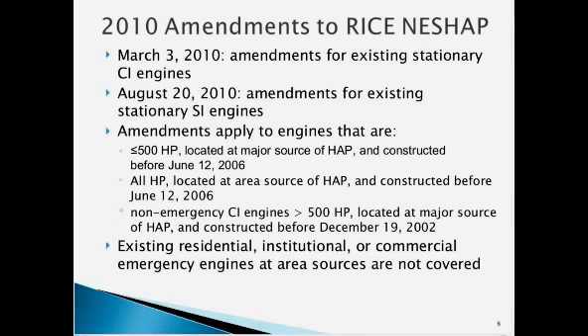What do I mean by existing? For the engines that are less than 500 horsepower located at a major source or any size located at an area source, existing means constructed before June 12, 2006. For the non-emergency CI engines greater than 500 horsepower at a major source, existing means constructed before December 19, 2002. And one thing I did want to note is that under these amendments, existing emergency engines at area sources that are residential, institutional, or commercial facilities are not covered by the amendments.